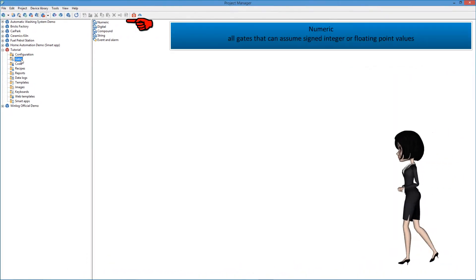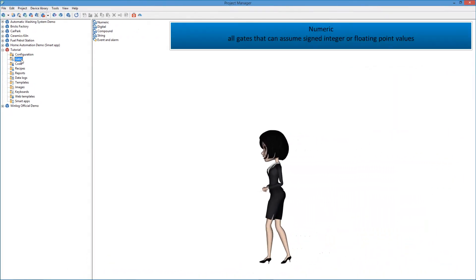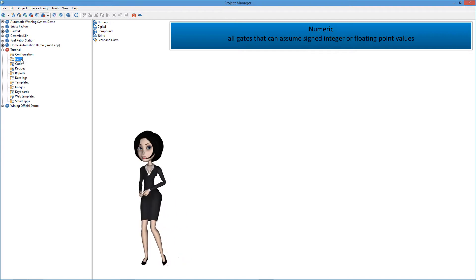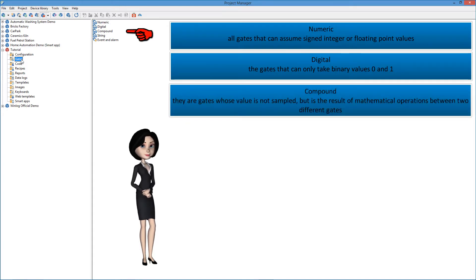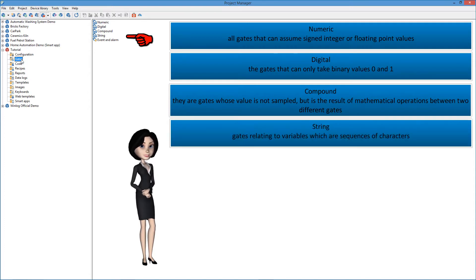Numeric: all gates that can assume signed integer or floating point values. Digital: gates that can only take binary values 0 and 1. Compound: gates whose value is not sampled, but is the result of mathematical operations between two different gates. String: gates relating to variables which are sequences of characters.